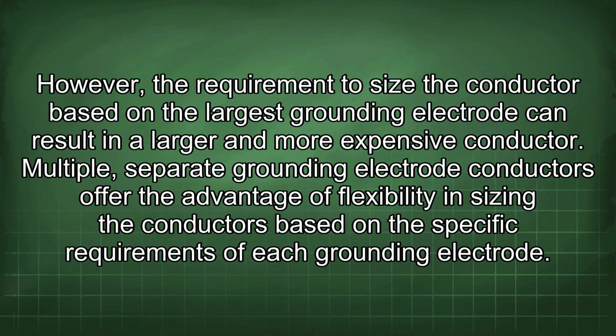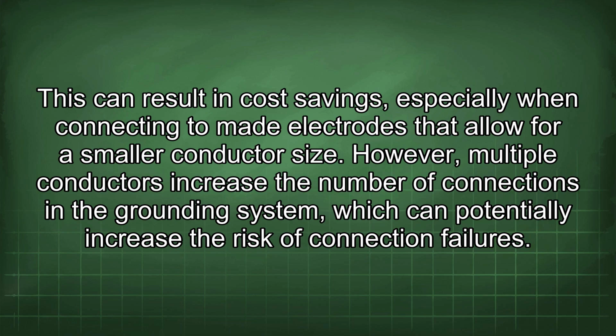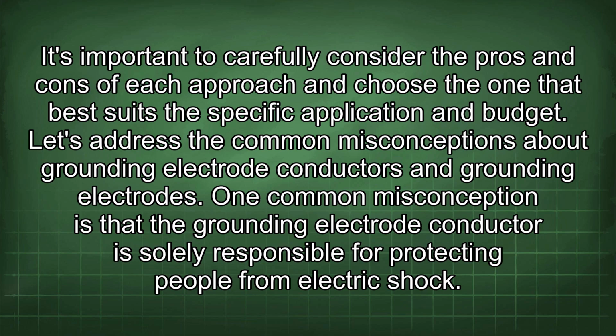However, the requirement to size the conductor based on the largest grounding electrode can result in a larger and more expensive conductor. Multiple, separate grounding electrode conductors offer the advantage of flexibility in sizing the conductors based on the specific requirements of each grounding electrode. This can result in cost savings, especially when connecting to made electrodes that allow for a smaller conductor size. However, multiple conductors increase the number of connections in the grounding system, which can potentially increase the risk of connection failures. It's important to carefully consider the pros and cons of each approach and choose the one that best suits the specific application and budget. Let's address the common misconceptions about grounding electrode conductors and grounding electrodes.